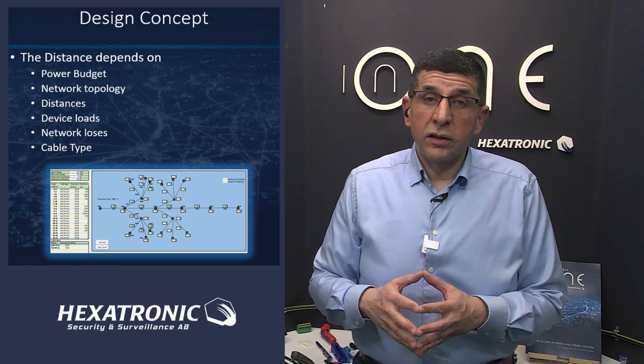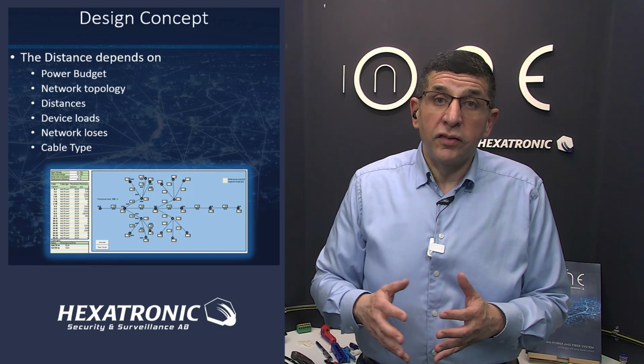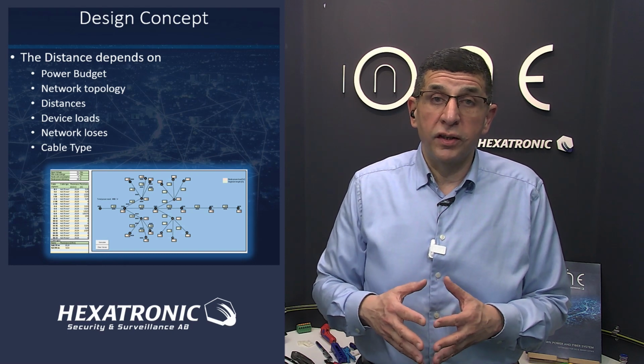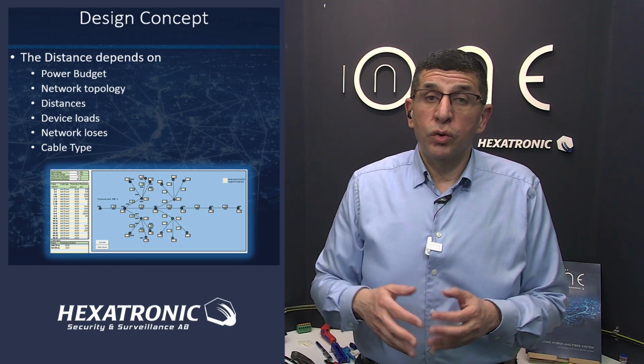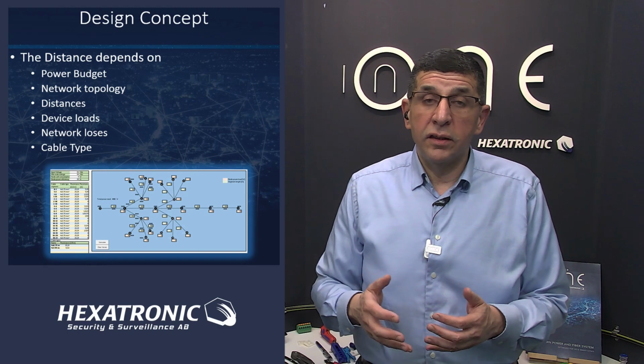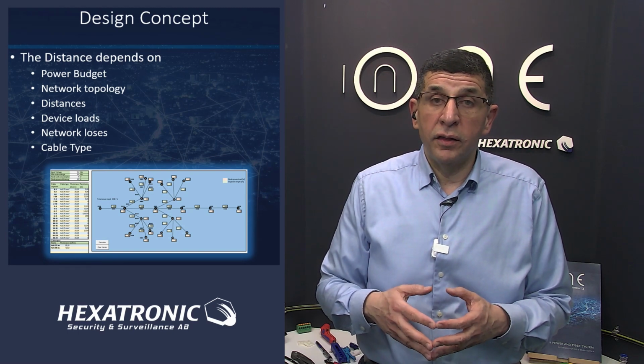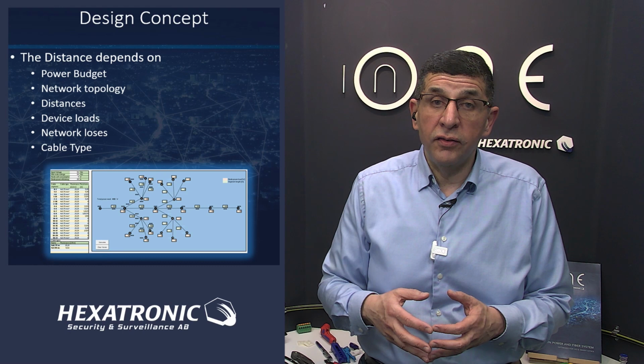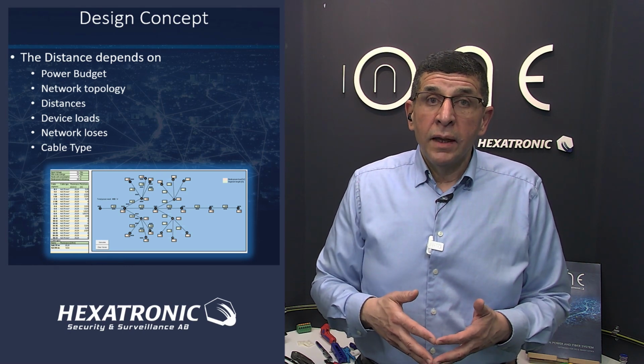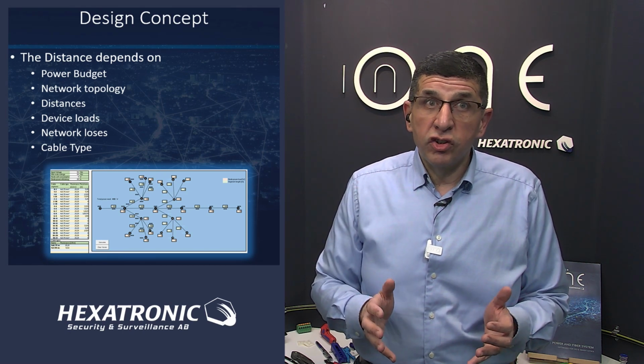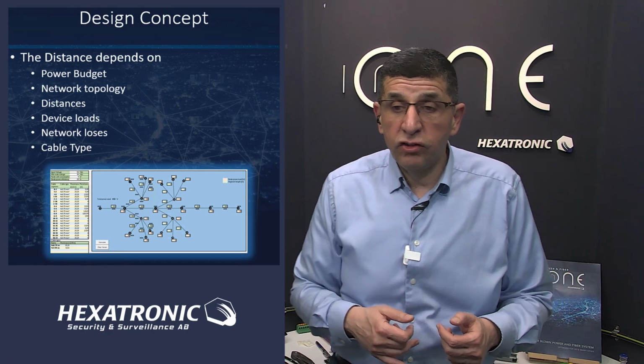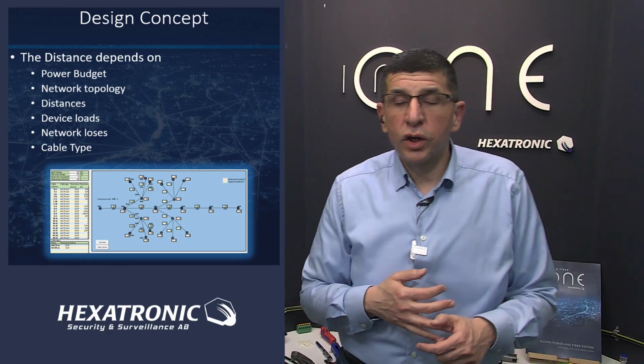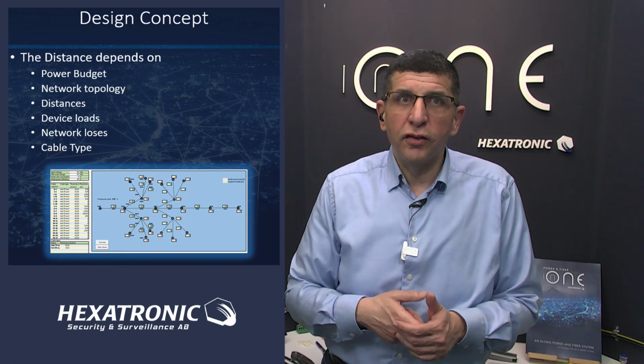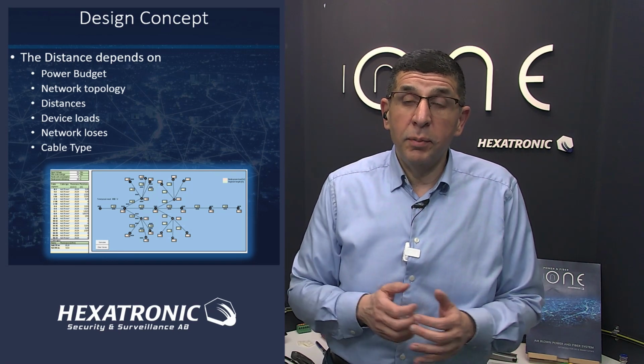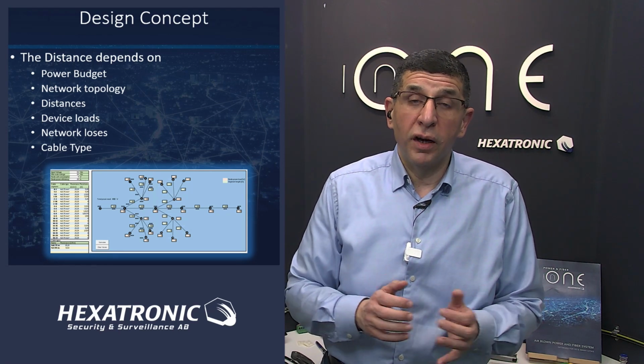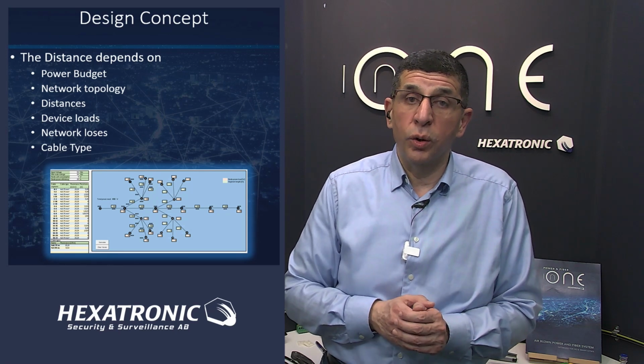The European safety standards allow up to 110 volts DC. So you start with 110 volts DC, and it depends on how many devices you have, the power consumption of each device, and the distances. We have made a calculation tool that takes into consideration the power budget, the network topology, the distances, the device loads, the network losses, and the cable type. Based on all of that, we provide the calculation, and we do that design for you.